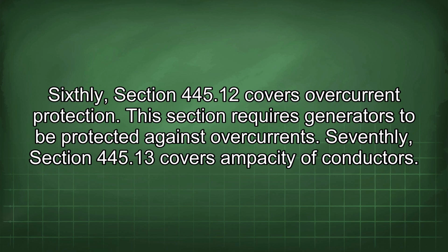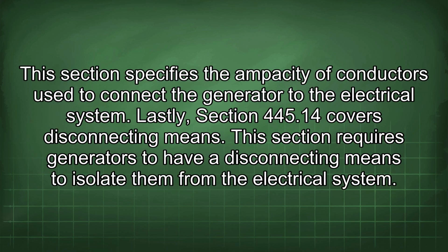Seventhly, Section 445.13 covers ampacity of conductors. This section specifies the ampacity of conductors used to connect the generator to the electrical system. Lastly, Section 445.14 covers disconnecting means. This section requires generators to have a disconnecting means to isolate them from the electrical system.